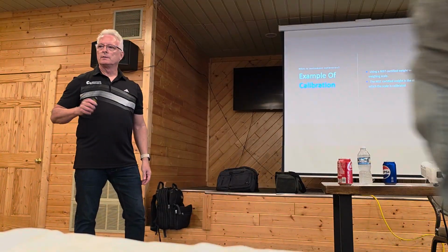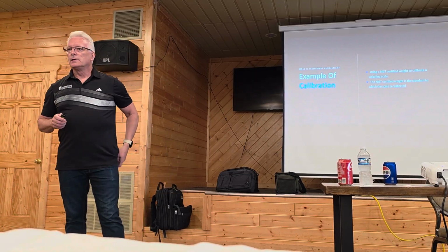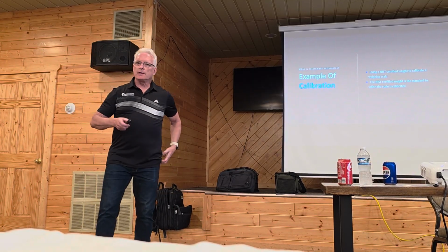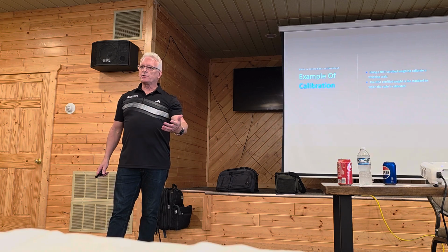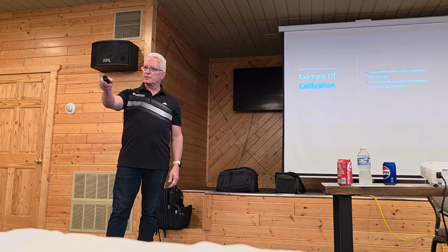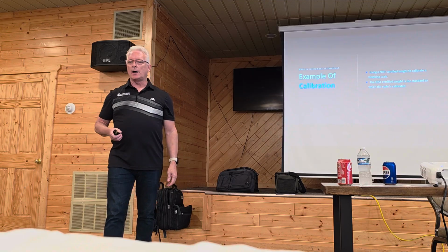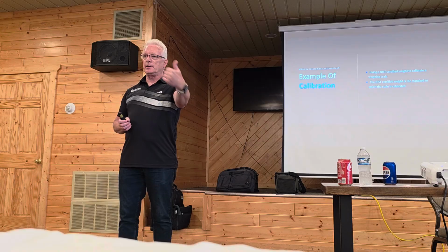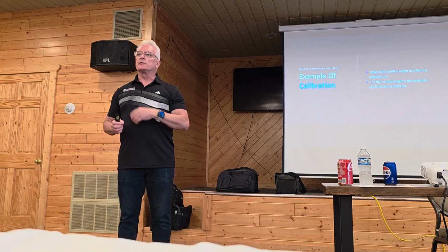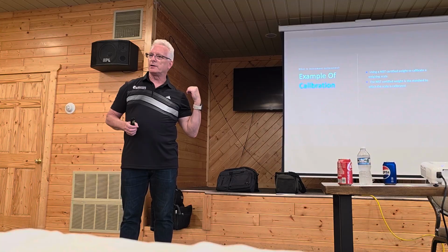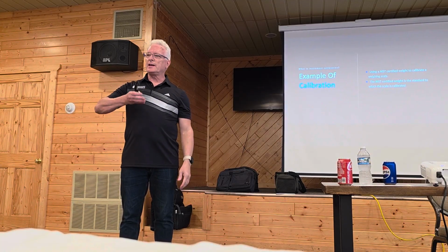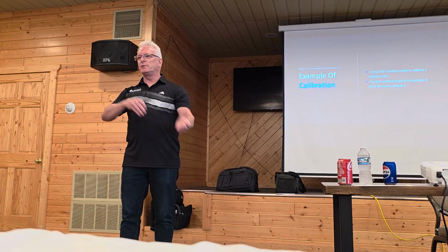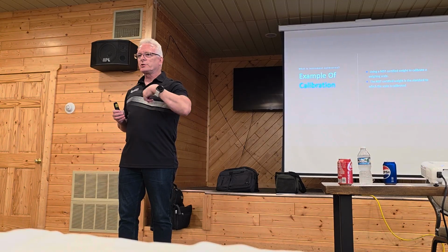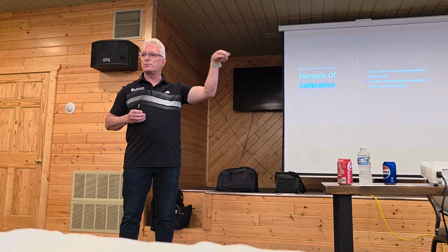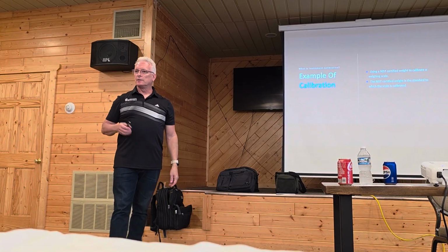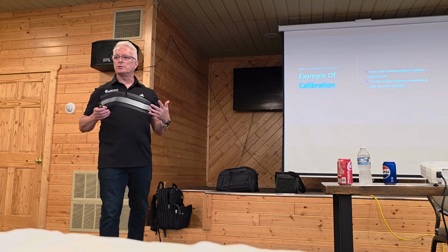So are you able to work with the SCADA integrator then? Yeah, that's a good point. So if we came the first time and found out ours is set up for 0 to 1,000 and yours is set up for 0 to 2,000, I can give you that information and you can call your integrator and say there's two different ways, you can change this or we can change it on the meter, which is the easiest way. So if we find out it wasn't set up right, we just change it in the meter to equal the system, and then we force it to send that signal through to make sure all the way through it's right.